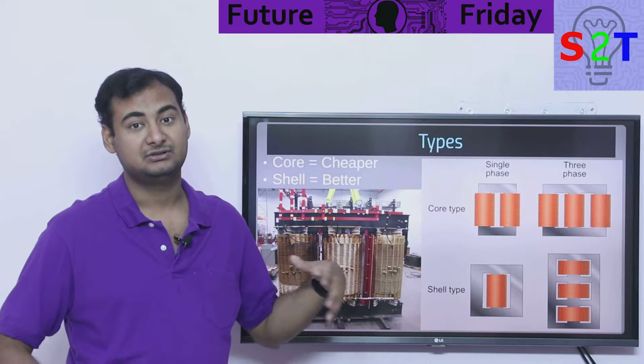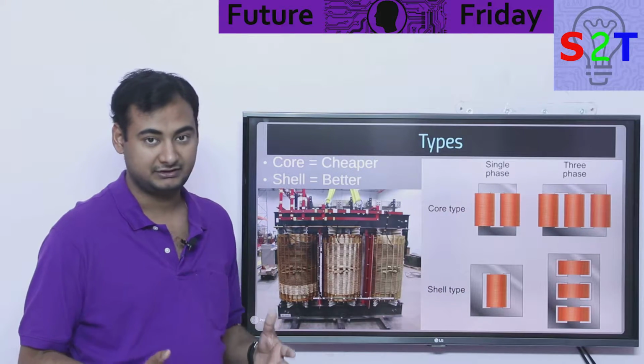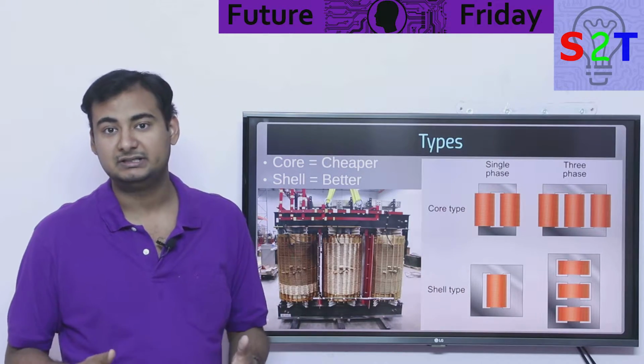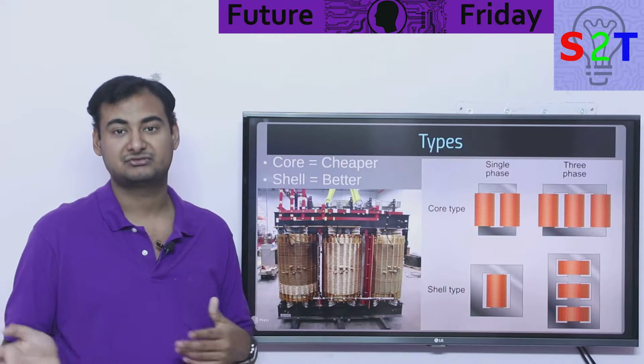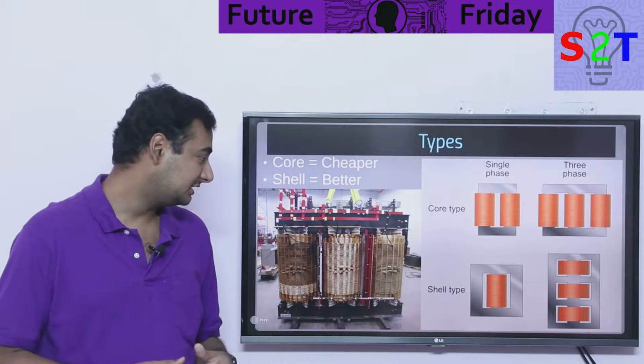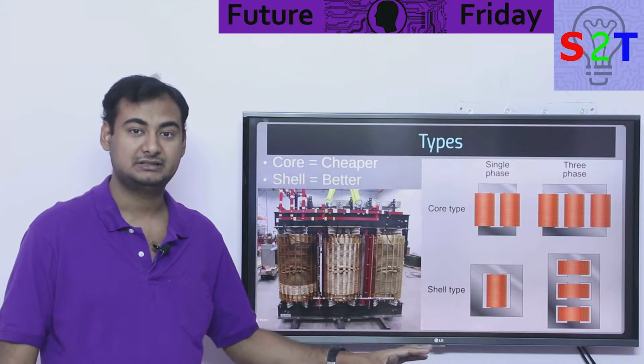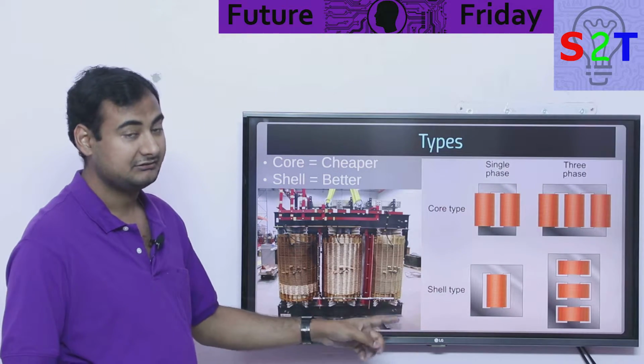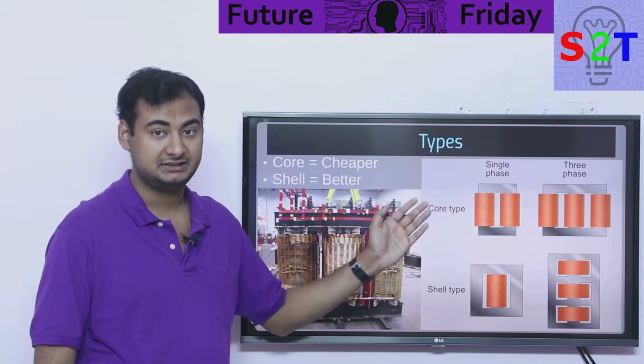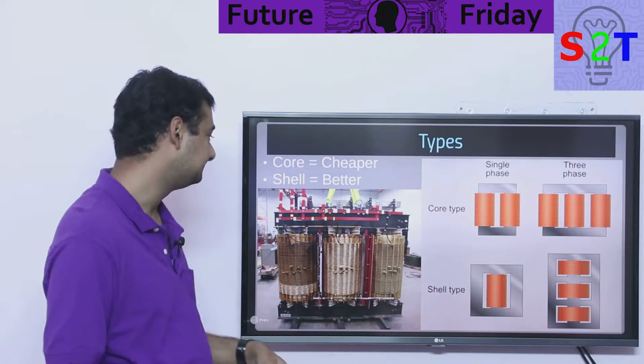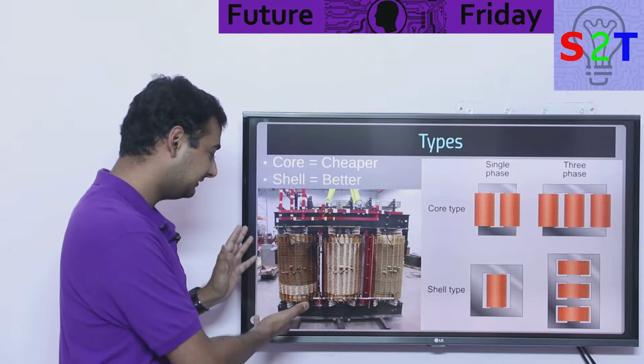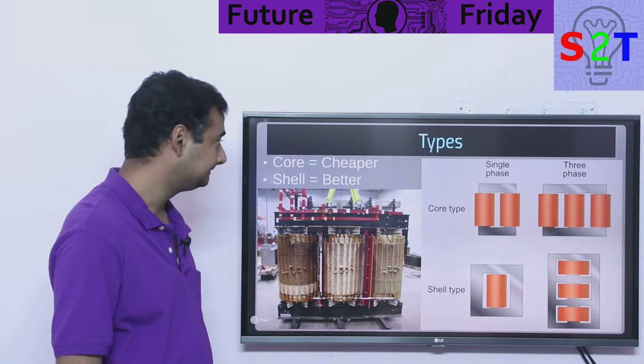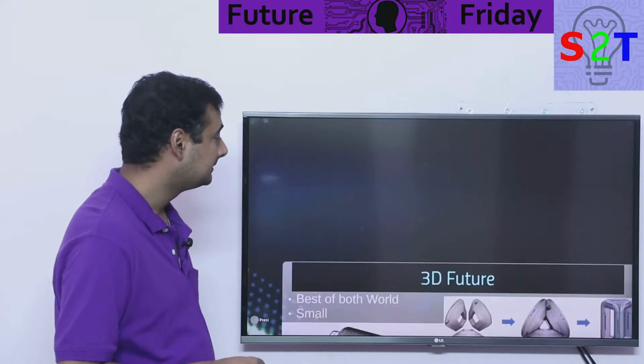Then you have shell type in very high application, very expensive transformers, which are generally needed when talking about hundreds of megawatts being transmitted. In those sort of scenarios, people generally try to use shell type, but be aware, because it requires more material, it is inherently more expensive. As you can see, these things become quite big and complex. So these are the types.